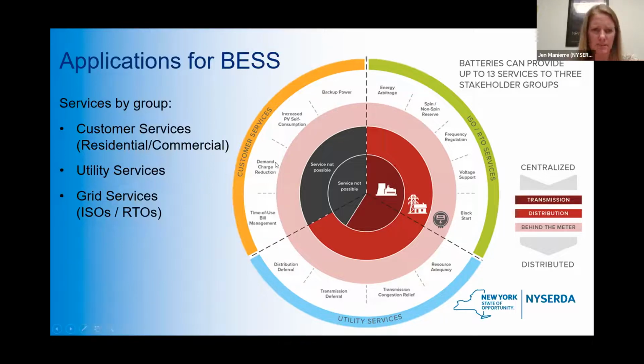Moving over to about between the 9 and 10 o'clock hour on this chart, demand charge reduction. Some larger commercial buildings are charged according to their demand. So wherever their largest demand for electricity is at any point in the day, there's a fee on their bill, basically, that they have to pay more based on the highest absolute time that they're using the most amount of energy. Some commercial establishments can reduce that demand charge if they look at when they're going to be using the most amount of electricity, or have the highest demand, and supplement it with battery backup that they charge during one of their lower consumption times and reduce that demand charge. So lots of different uses for it.